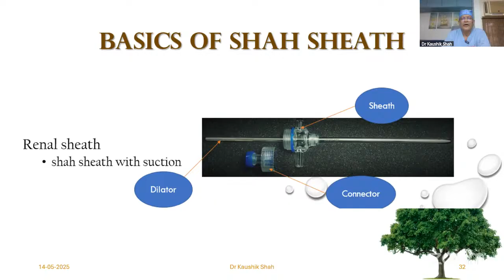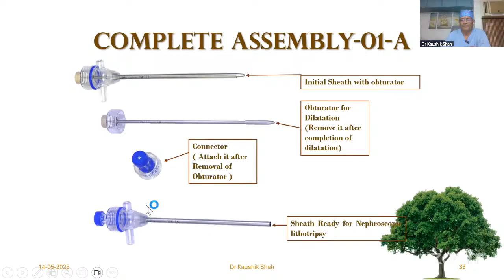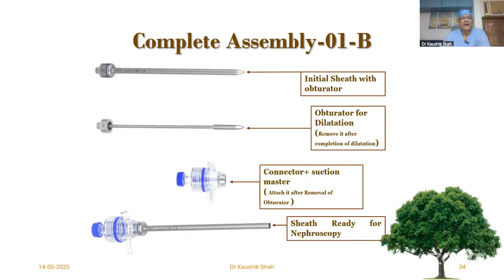Now, in one form, the suction master is attached to the sheath, and this is a dedicated dilator, and this makes a complete system. In another version, the suction master is not attached to the sheath, and therefore, in a multi-track PCNL, when you are putting multiple sheaths, the space is not occupied. Plus, this is also autoclavable, and we can use it again and again. You can use steam, plasma, or ETO. Everything is possible. So the complete scenario is that one is a non-autoclavable version where the suction master is fixed to the sheath, and in another it is separate.